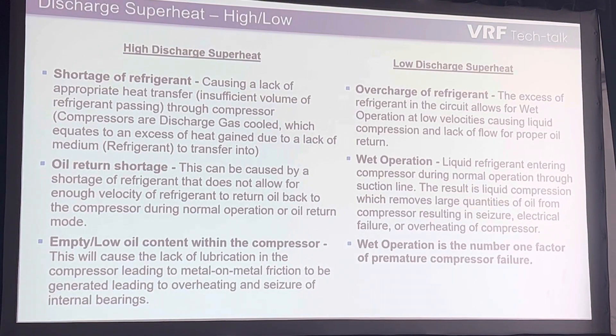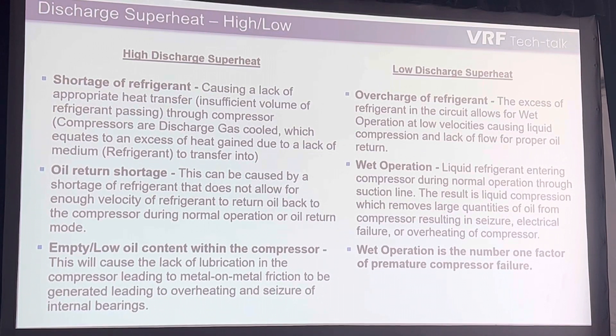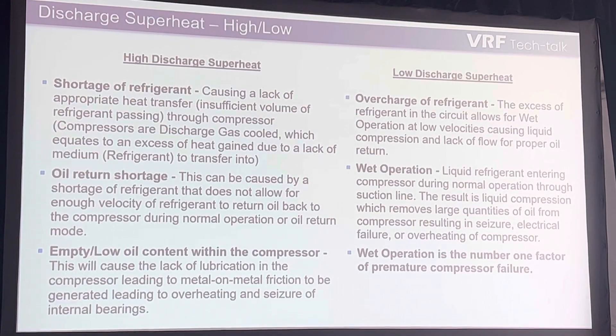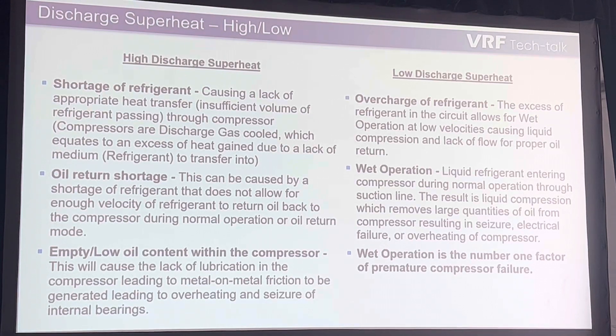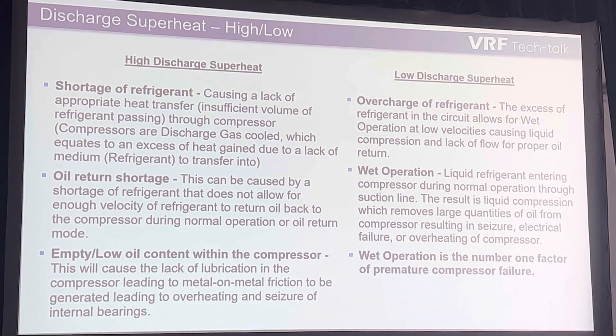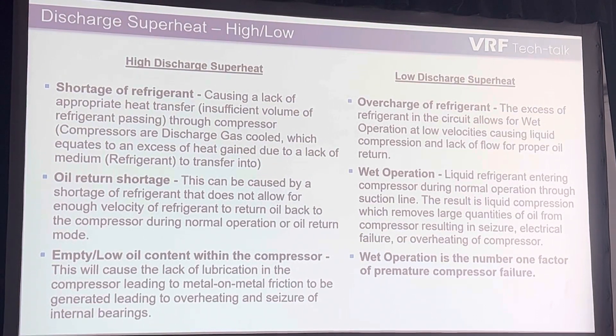You'll see this more often than not for maintenance — people not doing the due diligence of charging. 'I added 40 feet of line set. It's behind the driveway, no one's gonna find this.